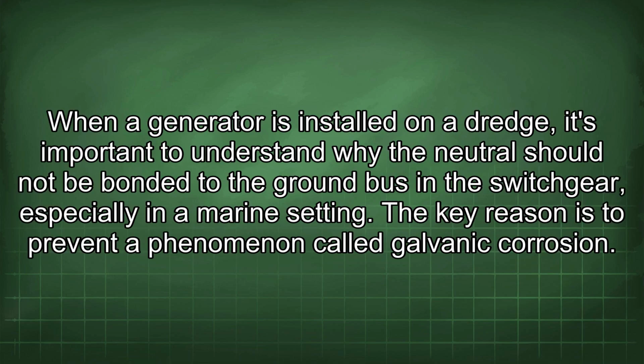When a generator is installed on a dredge, it's important to understand why the neutral should not be bonded to the ground bus in the switchgear, especially in a marine setting. A key reason is to prevent a phenomenon called galvanic corrosion.